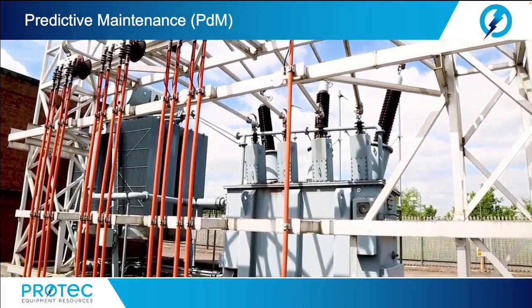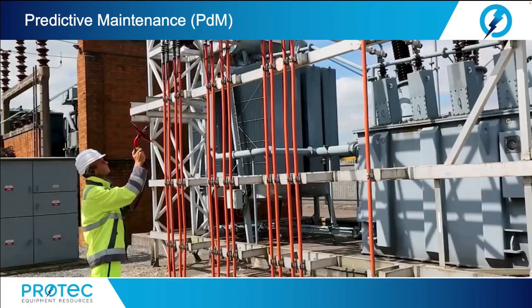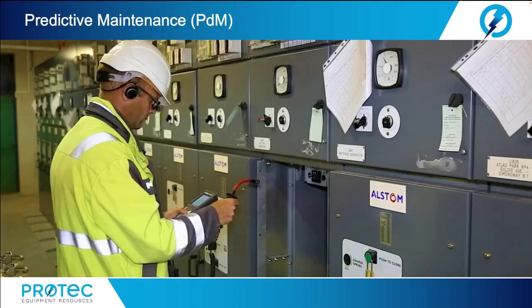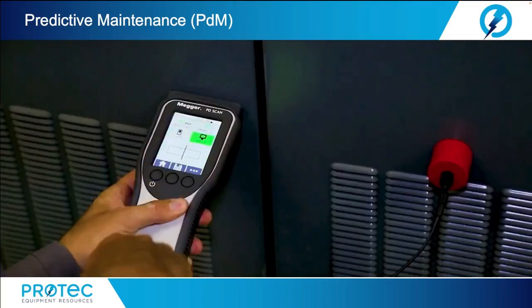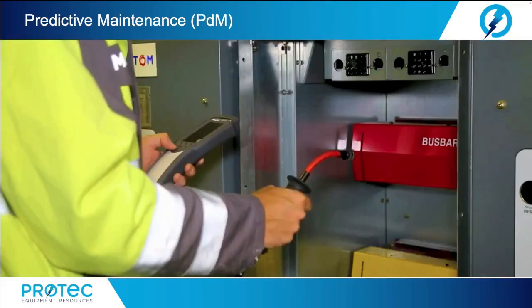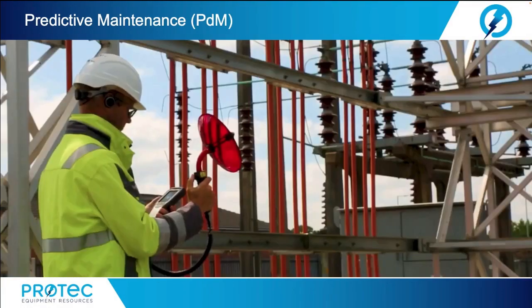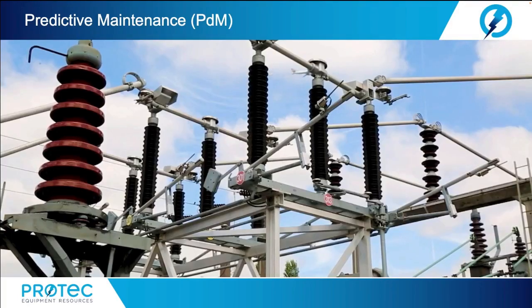Now, many of Protec Equipment Resources clients conduct maintenance service during large plant outages. Now, this is a wonderful opportunity to approach predictive maintenance services such as online PD surveys. Prior to the outage, the service company can conduct an online survey to obtain an early detection of the status of the insulation system. If issues are found, they can then focus time and effort during the outage to resolve these issues. This is also a value added in the final report offered to the client, where the service company can demonstrate their value in an as found and as left report.